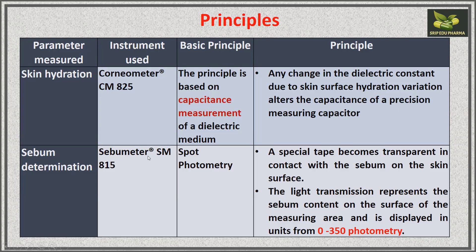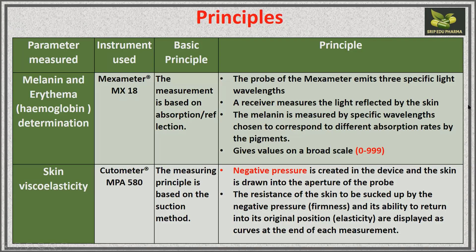Sebum determination is done with the sebumeter. Sebum means lipid, and a spot test is generally used for lipid determination — similar to how butter paper shows a spot when lipid is present. In the sebumeter, a special tape comes in contact with sebum and becomes transparent. The light transmission represents the sebum content on the surface of the measuring area, displayed in units from 0 to 350 by spot photometry.